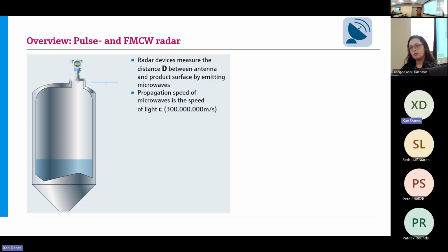Radars functionally or fundamentally, there are a couple things that don't necessarily change. If I look at the two commercially available level measurement technologies in this radar space, they both measure distance. Both a pulse and a frequency modulated continuous wave radar measure distance between the antenna and the product surface, and it's a speed-of-light based measurement. Those fixed values, the dielectric constant, the permeability, the speed of light, we really take for granted.